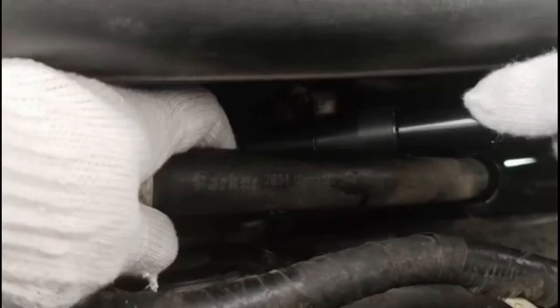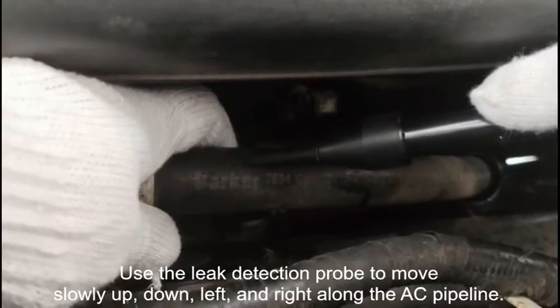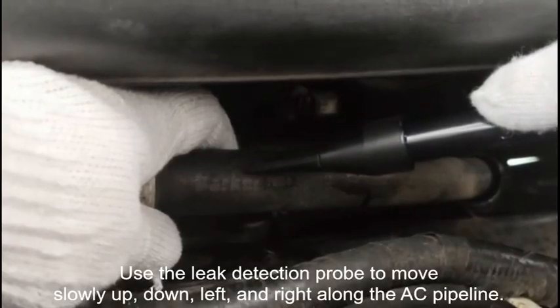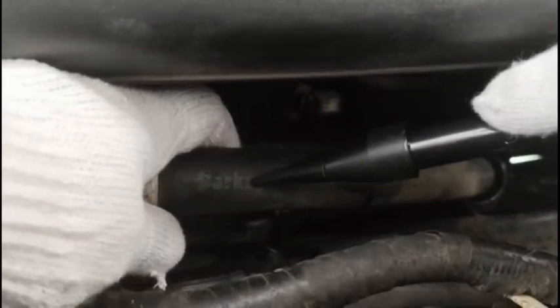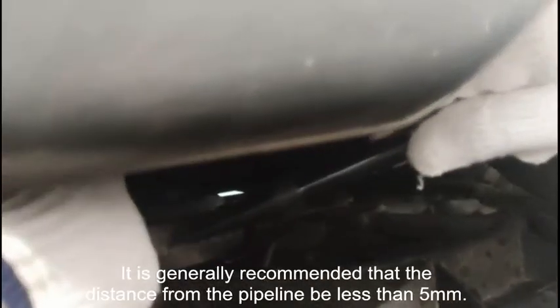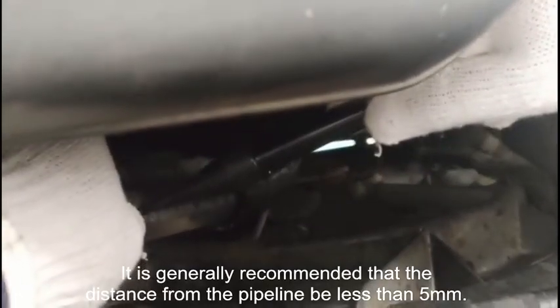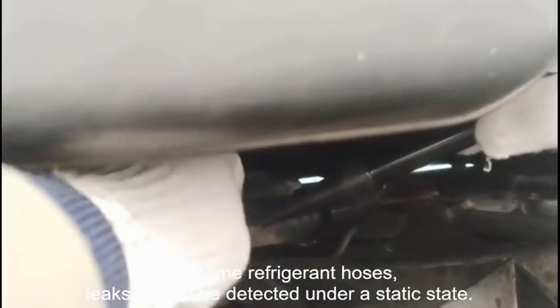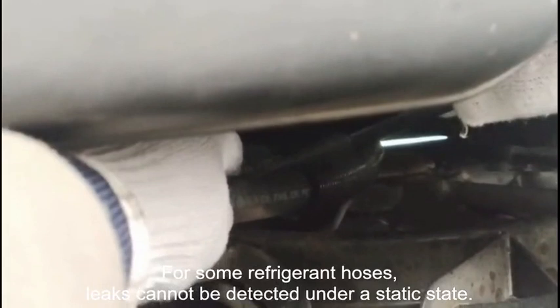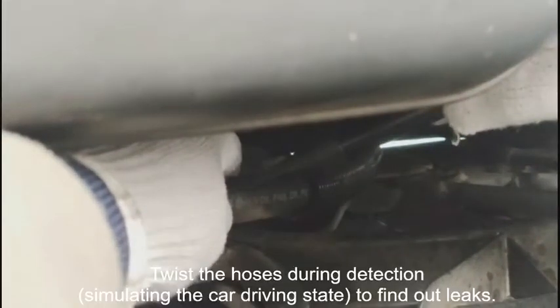Hose leak test. Use the leak detection probe to move slowly up, down, left, and right along the AC pipeline. It is generally recommended that the distance from the pipeline be less than 5 mm. For some refrigerant hoses, leaks cannot be detected under a static state. Twist the hoses during detection, simulating the car driving state, to find out leaks.